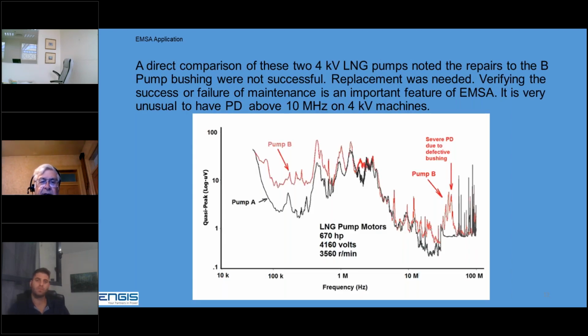At this site down in the Dominican Republic, they had 2 identical LNG pumps, cryogenic pumps. The Alpha pump is the black. Here's the FM radio stations. There's no AM radio station seen. The Baker pump, the red line, has higher activity, and very high activity out here at around 40 or 50 megahertz. It's very unusual to get very high frequencies out of 4 kV machines.